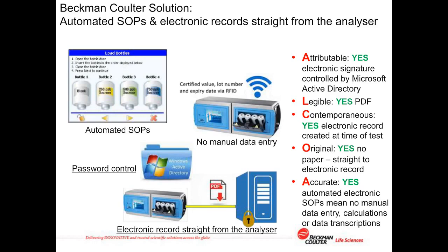Great. Here's an important question. Does the Anatel TOC tell me when something is wrong, or do I have to check the PDF output? Okay, so you can. If you're concerned, for instance, that it was making TOC or conductivity measurements that were past your alert level or your alarm level, so you needed to know about them, the Anatel can tell you this. It can be configured so that it automatically sends a digital signal to your PLC or SCADA system to tell you there's an alarm, effectively, or an alert on the PAT700. So you don't have to wait for the PDF file to come out to you. It'll tell you. It can also be configured to do the same thing on the analog outputs. The 4 to 20 milliamp outputs can warn you with an alarm as well.